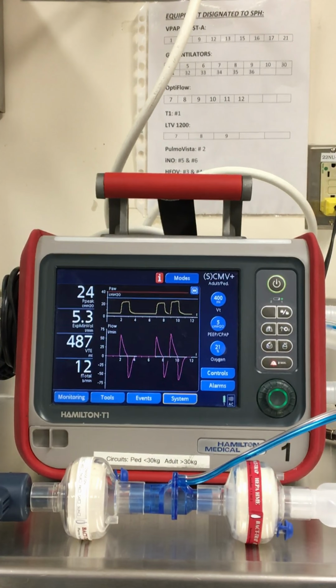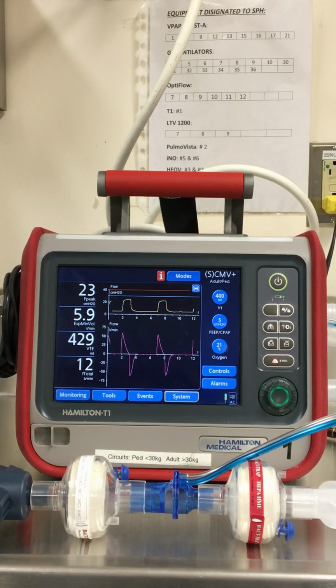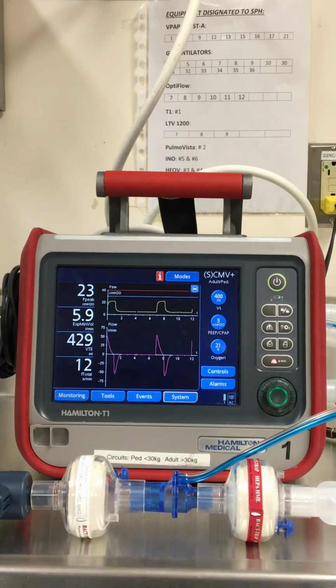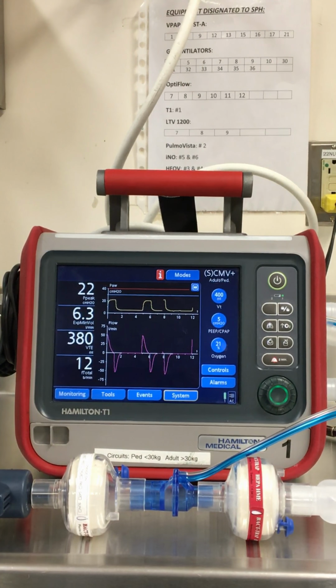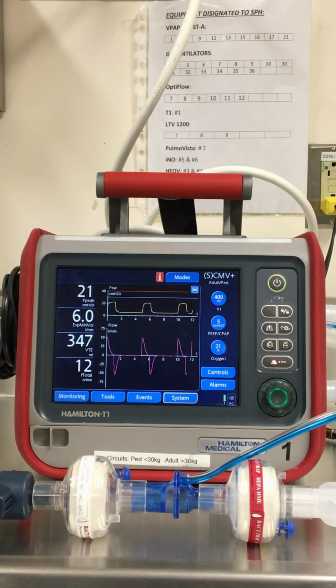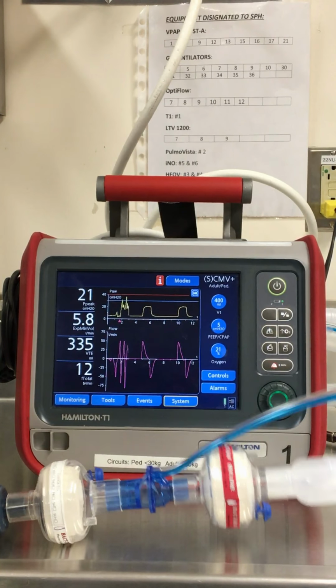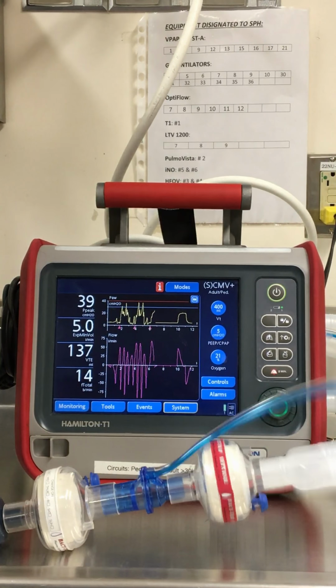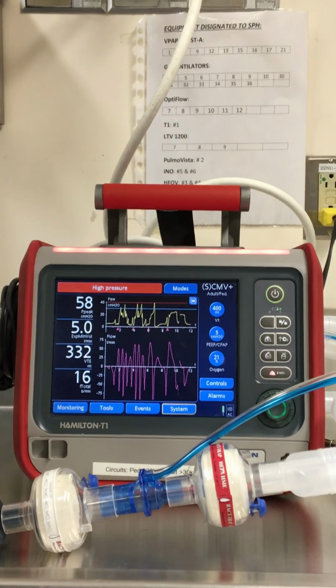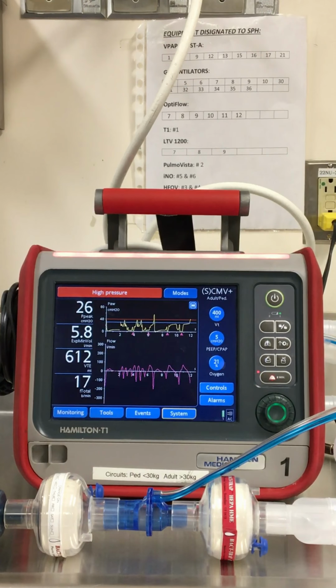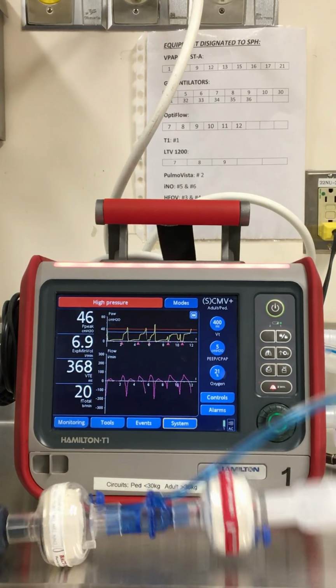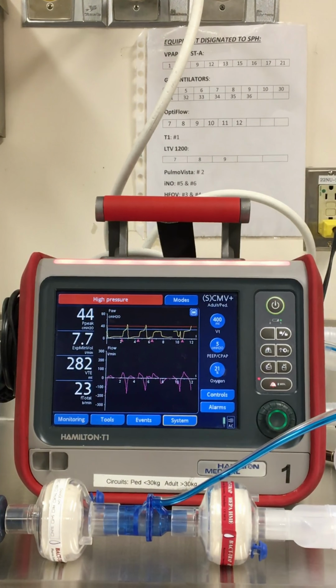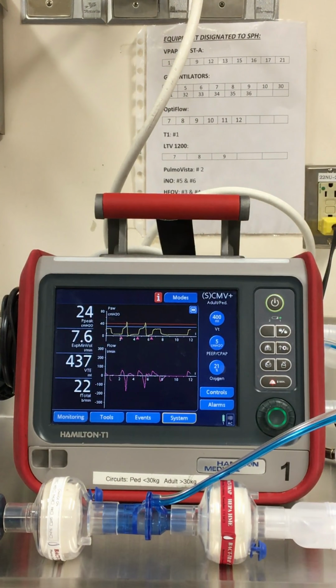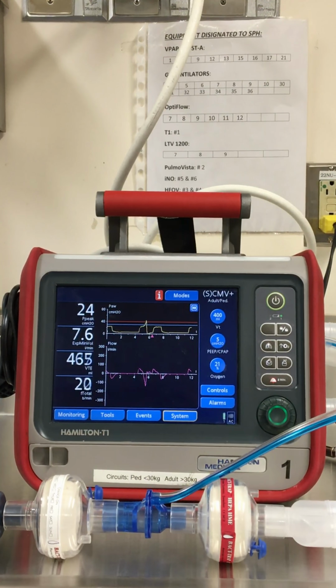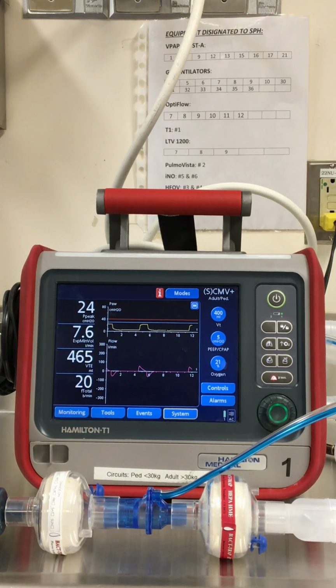The next type of alarm, and I'm just going to clear my silencing, is the high pressure alarm. Typically you're going to see this when your patient coughs, if they're waking from sedation, again, and their breathing is very inconsistent, or if they're bearing down against the breath of the ventilator. Just some examples of when you might see this. So I will now try to demonstrate a high pressure alarm. And this is a high pressure alarm. You can see our waveforms have changed drastically, and this is very common with a cough in your patient. Once the issue has been fixed, or say the patient stops coughing, again, the ventilator will correct itself over a few breaths back to whatever normal ventilation was based on the mode prior to the alarm.